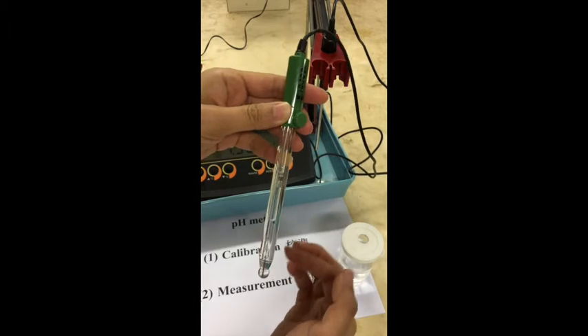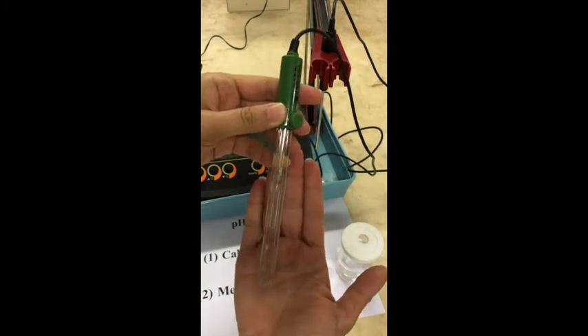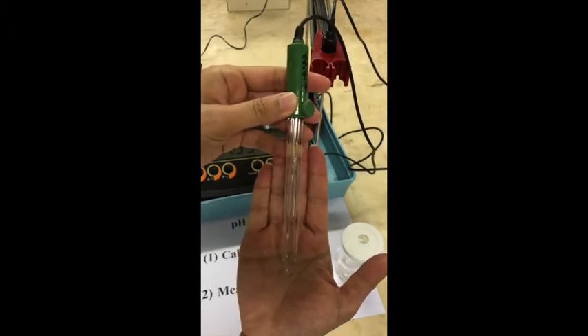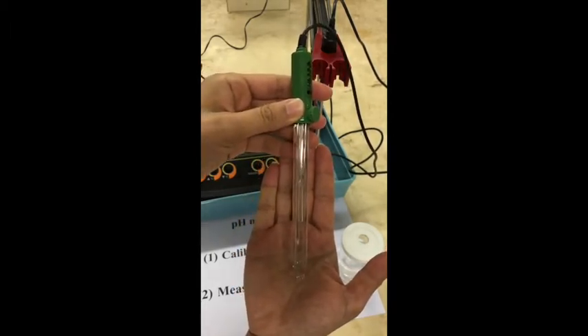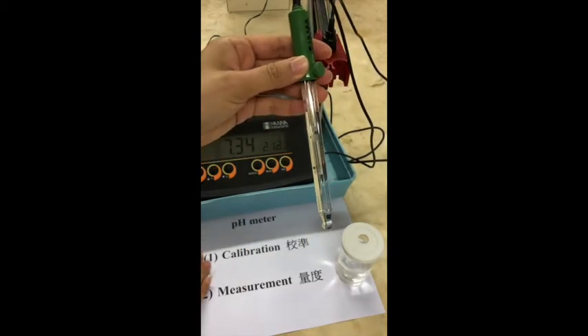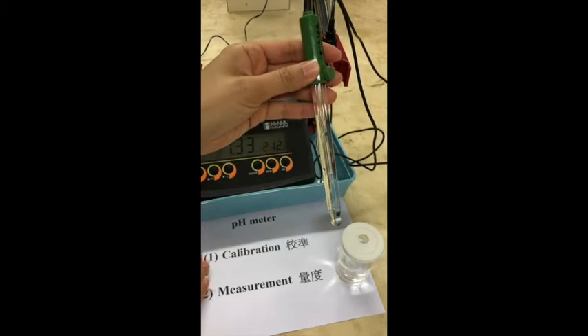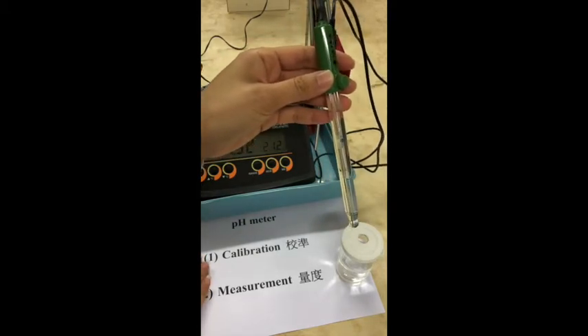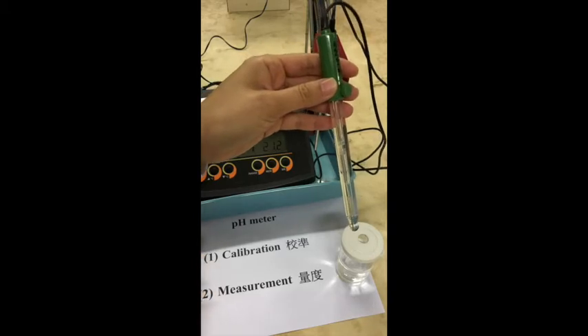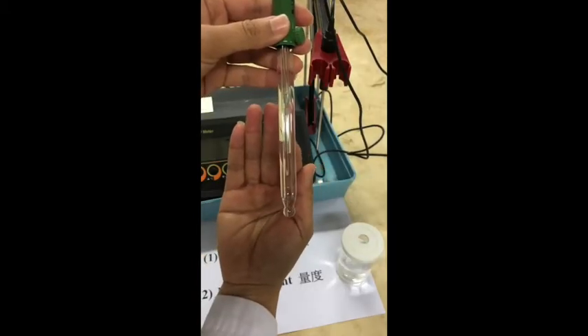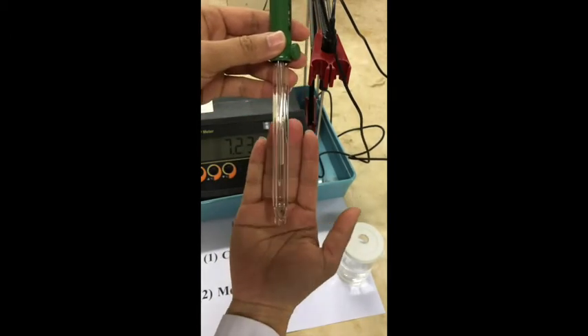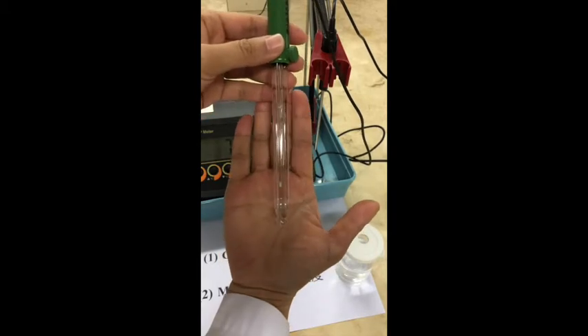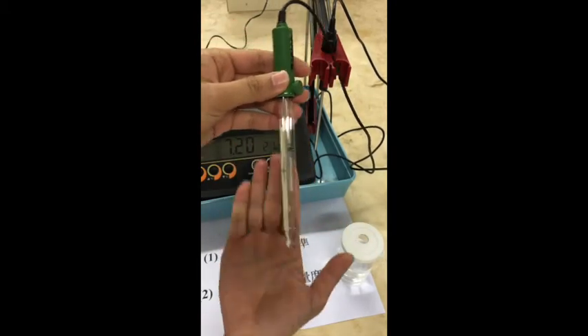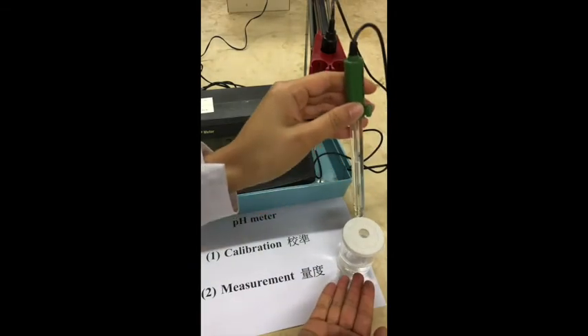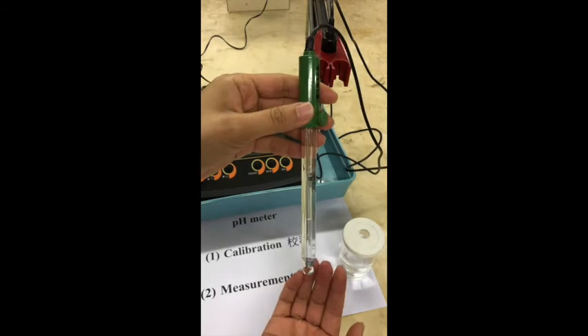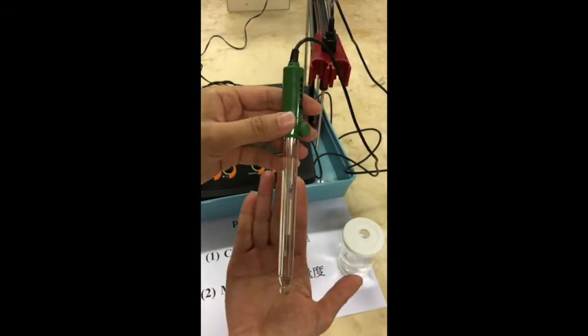The electrode potential of the probe depends on the condition of the boundary of the glass and the solution inside the probe. The calibration has to be conducted if the pH meter is switched off or idle for a long time, as the condition of the probe may change. The liquid level inside the electrode will be lower if the glass is dry. That's why we have to place the electrode inside the DI water when it's idle. If the liquid level changes, the electrode potential of the probe also changes.